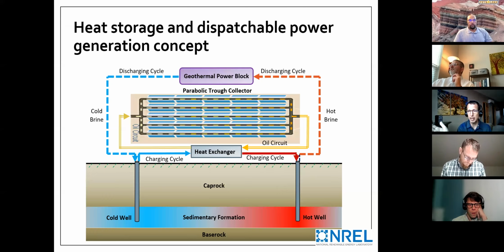So we've started with the formation, and we're going to have two types of wells: hot wells and cold wells. The hot wells are always hot and the cold wells are always cold, in a double push-pull arrangement—huff puff, however you want to phrase it. First we flow hot fluid into the hot well, then flow hot fluid out of the hot well; we flow cold fluid out of the cold well, then flow cold, cooled geothermal fluid back into the cold well. They're both doing this, and that has a lot of advantages for the performance of the overall system.